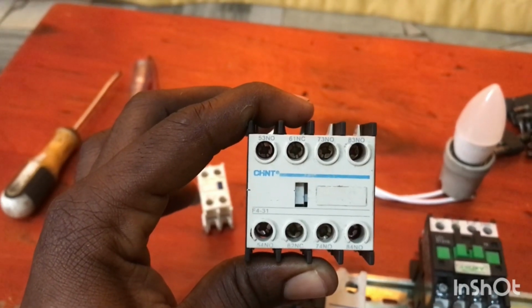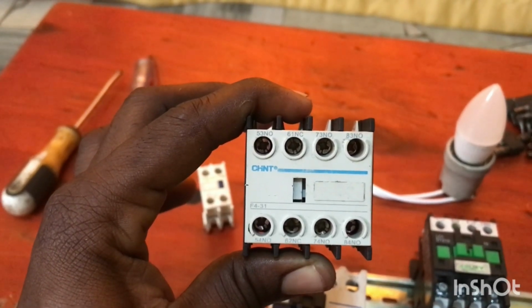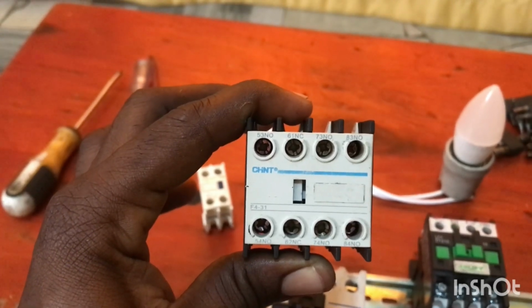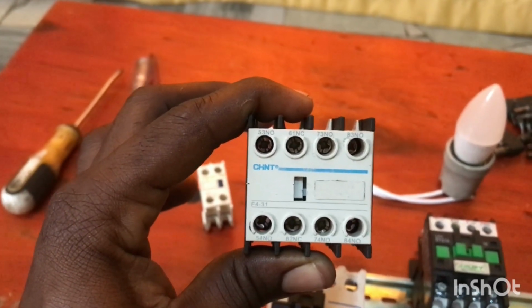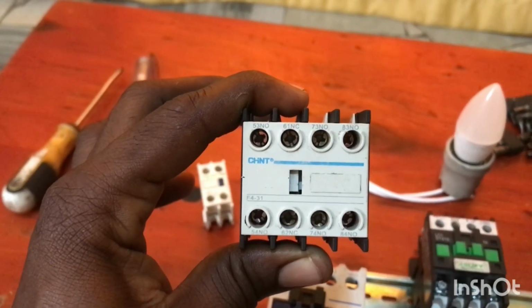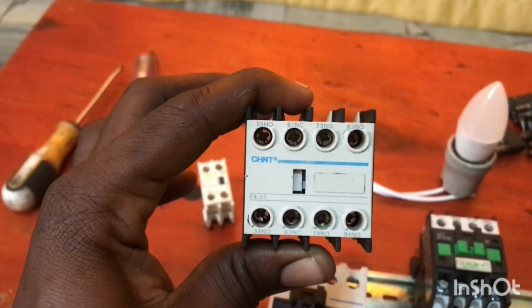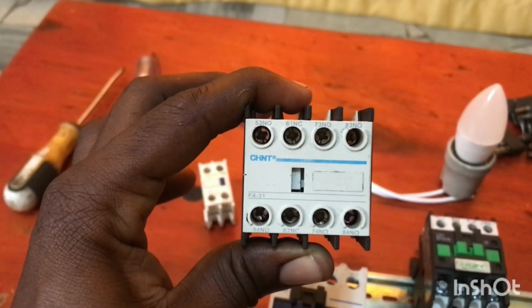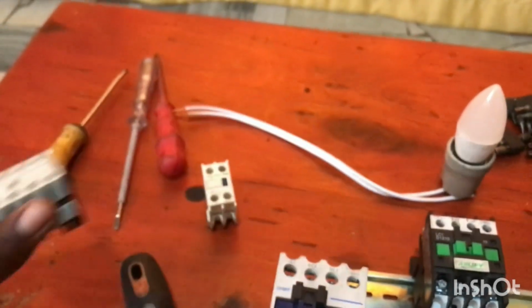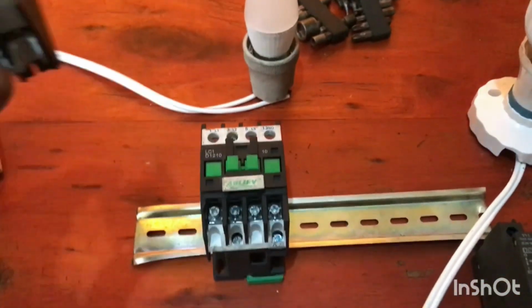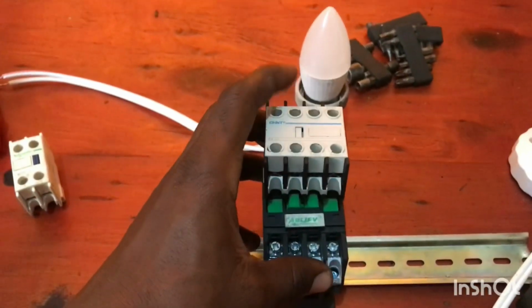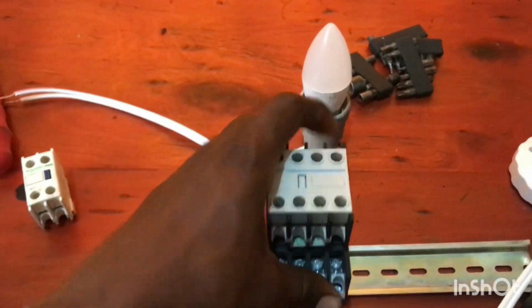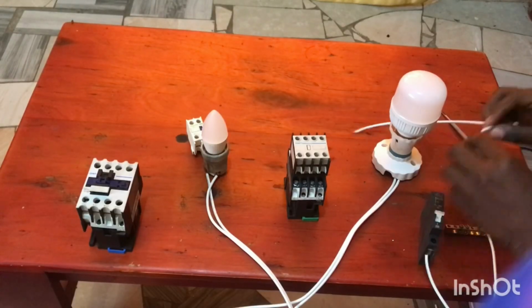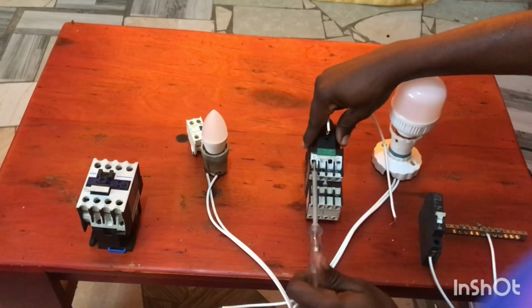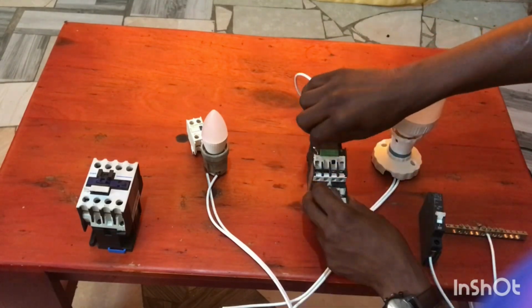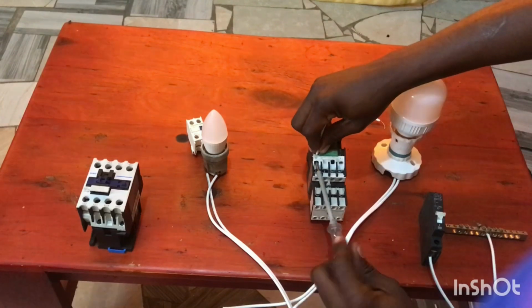The work of this contactor and auxiliary is either to switch on or to switch off. It can be a generator, it can be a motor, a machine. We can connect it so as to switch on or off at a certain period when it gets energized. That is the work of it. So I'm going to connect two lights on normally open and normally closed, meaning those lights will not work at the same time. When the contactor gets energized, one light should go on while the other one goes off. We are going to see how we can do that.